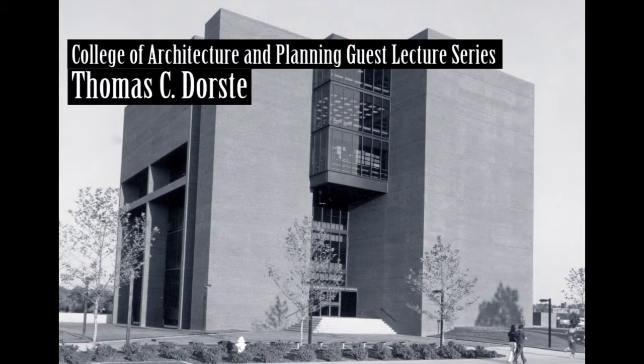But anyway, what it wound up with was we could turn that building down for cleaning purposes with one switch to one-third of the lights for cleaning after the occupant had left. Whereas under normal conditions, the cleaning people turn all the lights on, leave them on until 2 o'clock in the morning, and then turn them off when they go home. But with master control, all they can do is turn on one-third of the lights, which is adequate for their cleaning.